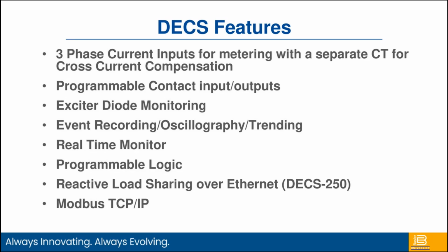So we talked about diode monitoring. We can also have much better event recording, so we can know what happened in the system during normal operations or, in particular, in fault conditions. The real-time monitor is very useful during troubleshooting and tuning. We have programmable logic, so we have integrated PLCs basically. And as I talked about, we're able to do reactive load sharing over Ethernet, and also communications back to SCADA systems or monitoring devices through Modbus RTU or Modbus TCP/IP.